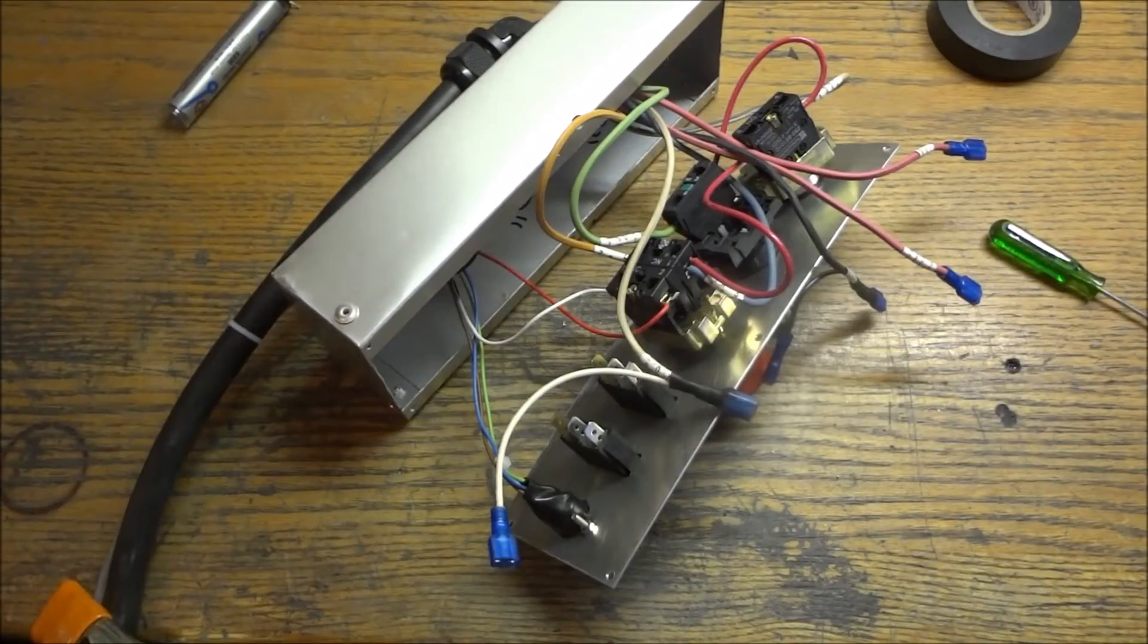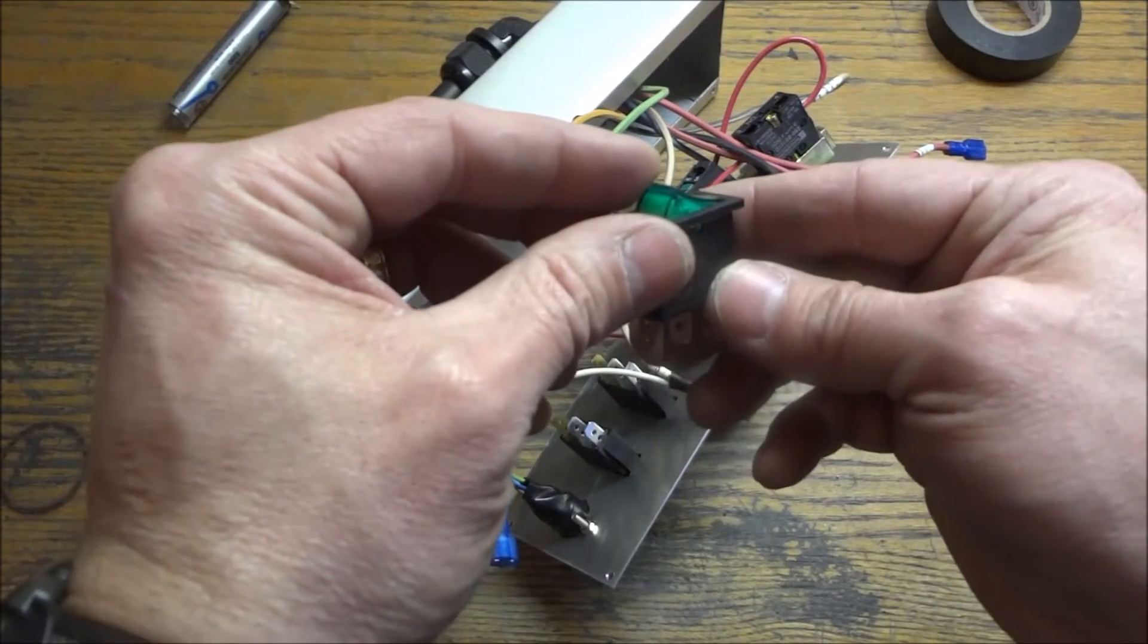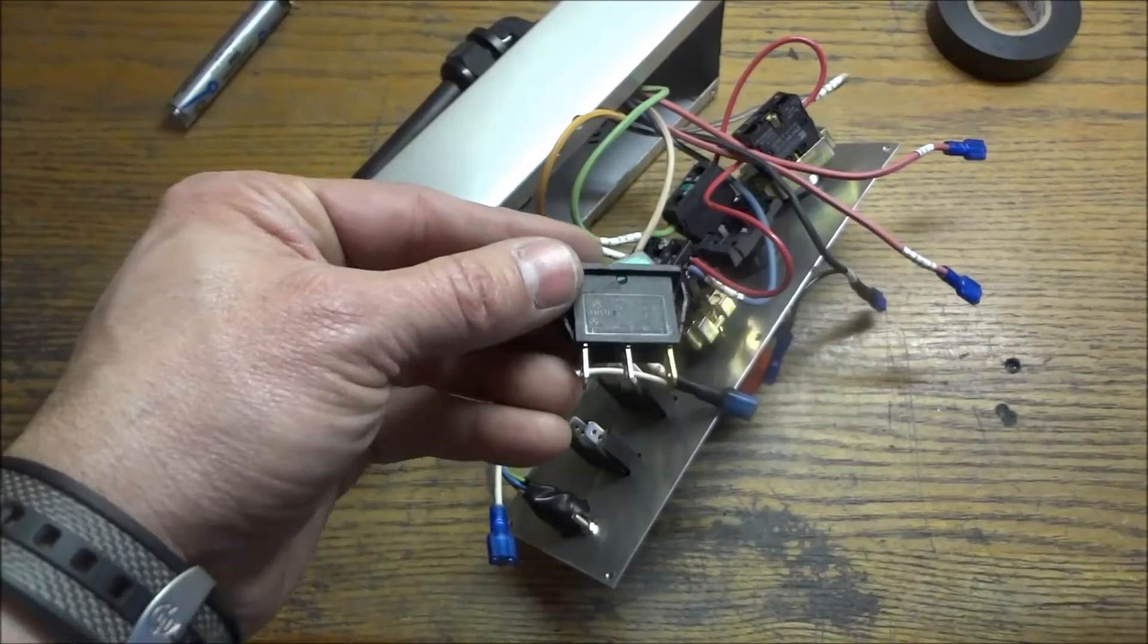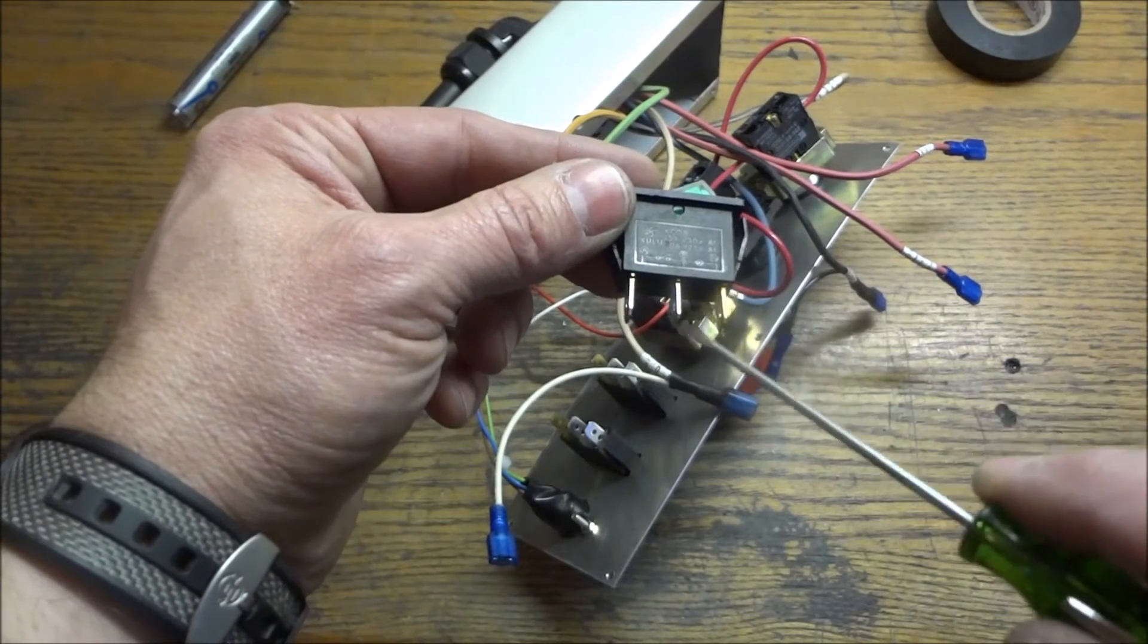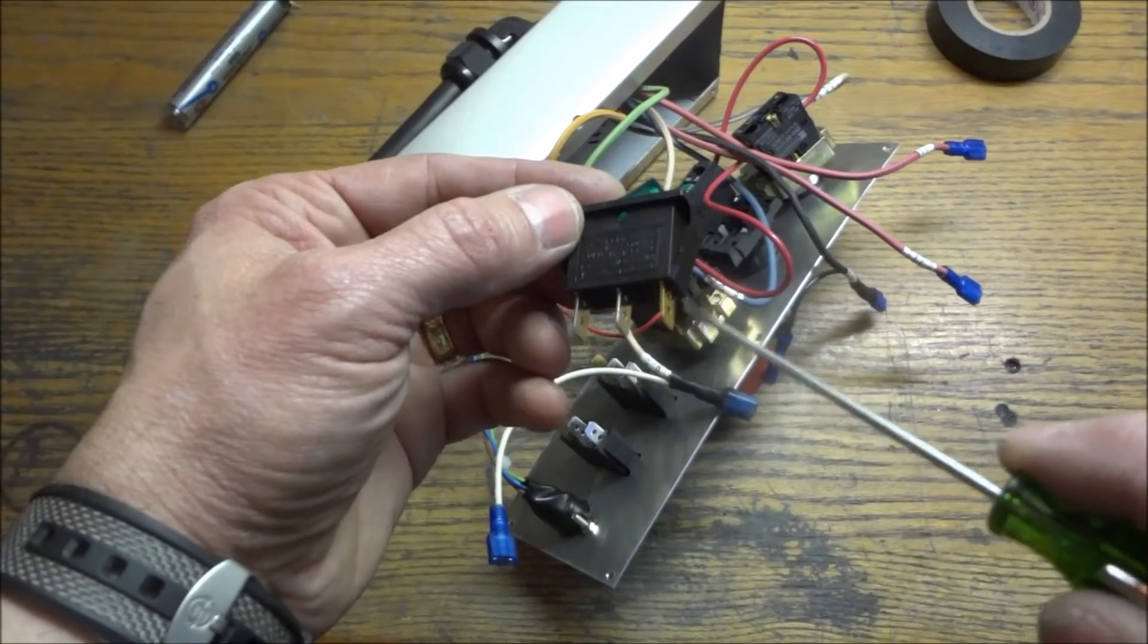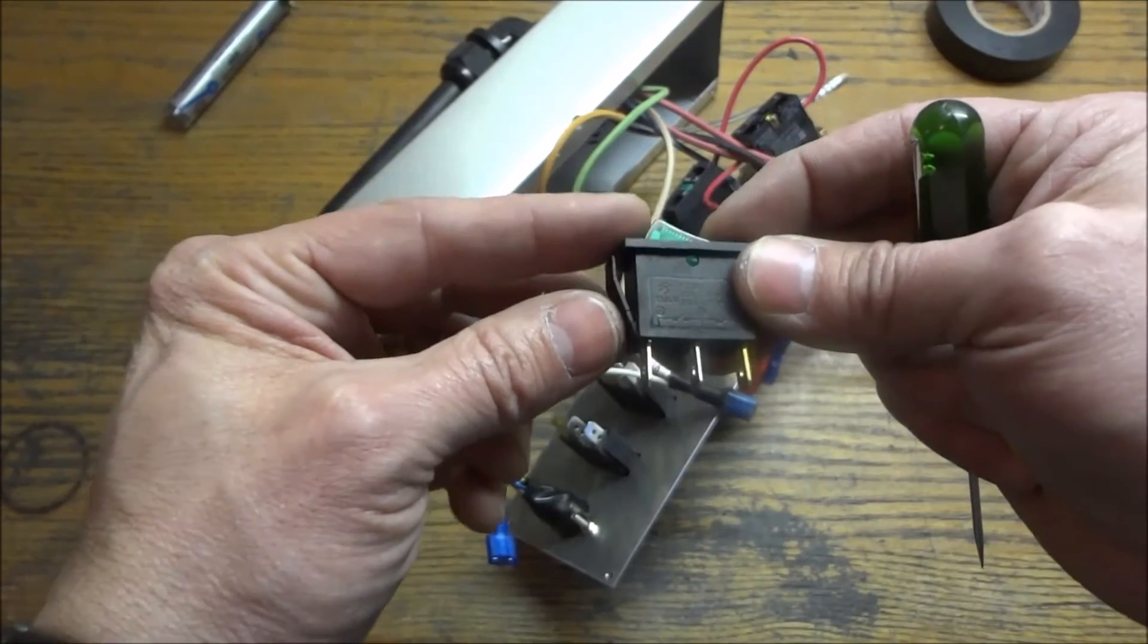So all we have left now to connect is our two rocker switches, one for our coolant and one for our computer. Now the way these rocker switches work, they're illuminated. So there's a little LED or SMD inside there and it comes on whenever there is a load. So the way they're connected, pin A is 110 volts coming in, then it's switched. And then the center pin here goes out to your load. And then on this gold colored pin, you need to have a neutral. And that will allow the switch to operate and the light to come on.